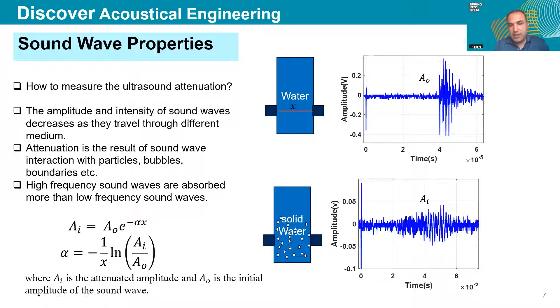To start with, the basic principle of ultrasound imaging is very important for you to understand, so you know how ultrasound imaging works, understand the ultrasound signal, and can apply it to different systems. So simply, this is a container with droplets and water. This is a wall of, let's say, the pipe, and you have an ultrasonic sensor attached to it. Use ultrasound gel between the sensor and the pipe wall to reduce the air trapped between them, because ultrasound is highly attenuated in air.